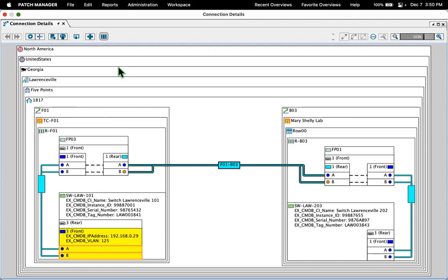We are thrilled when a company says they have all the data, it's in spreadsheets. It's usually about 75 or 80% accurate. They still have to go out and audit. Once, it wasn't even that close. We had it all in spreadsheets, but we were what, about 10% accurate? Well, the challenge is you say it's 75% accurate, but you've got 3 cables. Well, if you start adding cables up and you've got 3 out of every 4 of those are right, all of a sudden you've started to get where you've got no full traces that are actually correct.